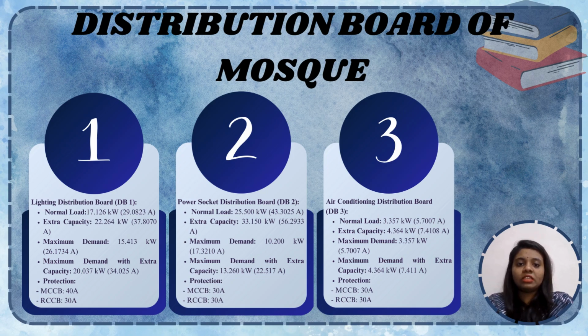26.1734 ampere. Rising to 20.037 kW and 34.025 ampere under peak condition, the DB is protected by a 40 ampere MCCB and a 30 ampere RCCB. Second one is the power socket DB.